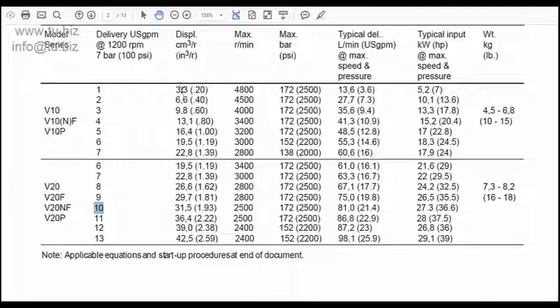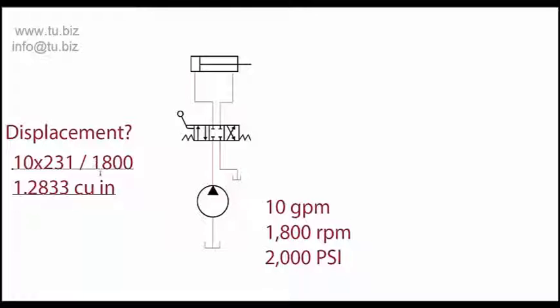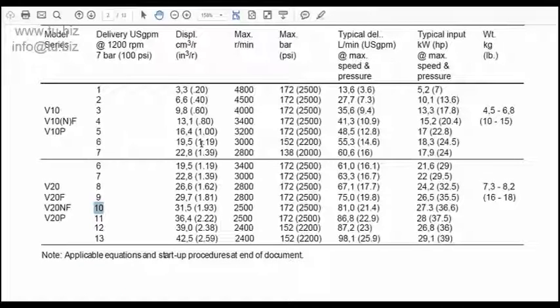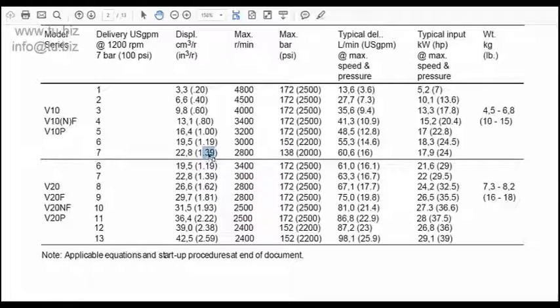We go to the next column and look at the actual displacement of the pump — that's the number we should focus on. The number we're looking for is 1.28 cubic inches. Looking at the catalog, we see a 1.19 — that's a little bit smaller. I don't want something smaller; I want something a little bigger. This one here is 1.39 cubic inches, so I'd be more interested in that pump.